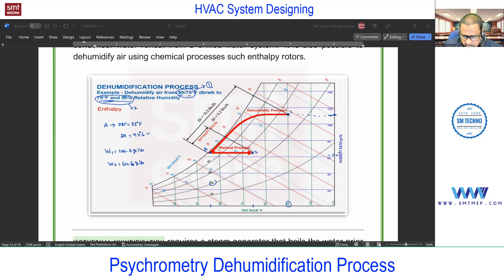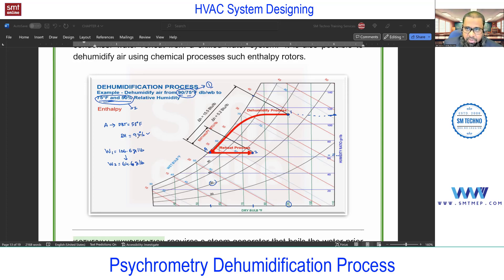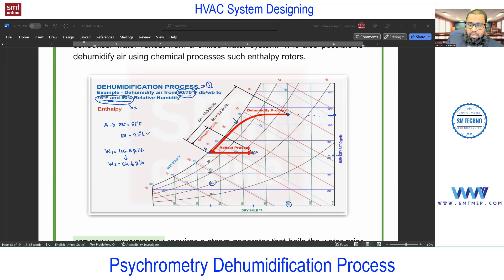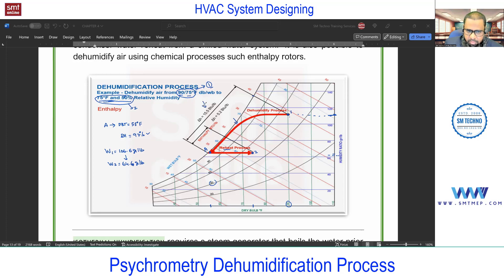To reduce the humidity ratio we over-cool the air. For comfort, at the maintained temperature the RH should be between 30% and 60% — in this example, 50%. Process 1 to A uses the cooling coil; process A to 2 uses the heating coil, which we call the reheat coil — because we first cool then reheat. In actual practice this coil is called the reheat coil.